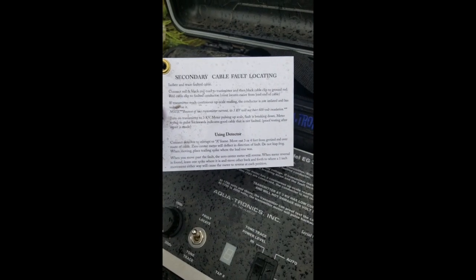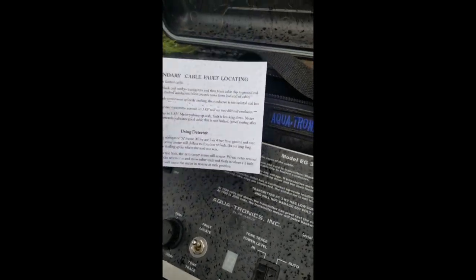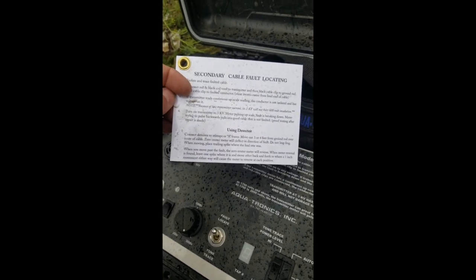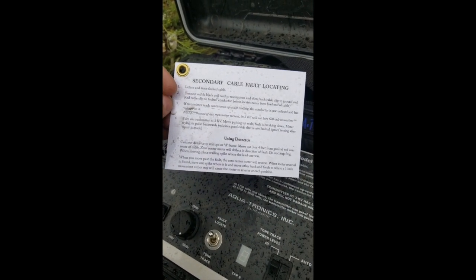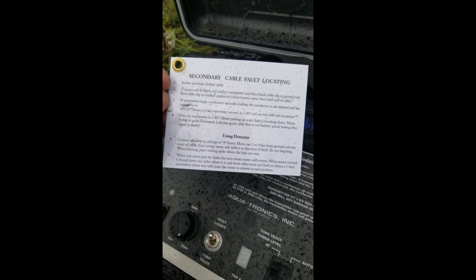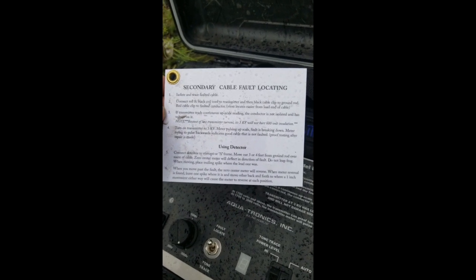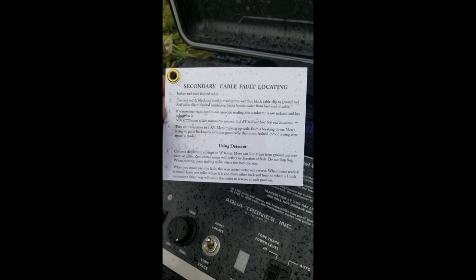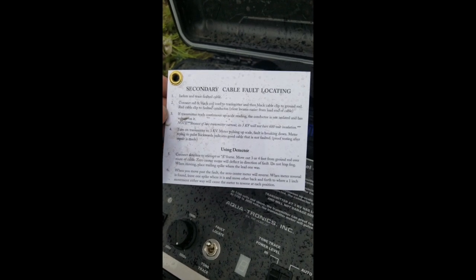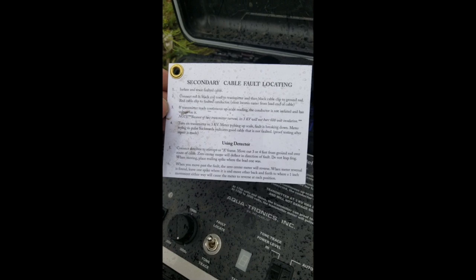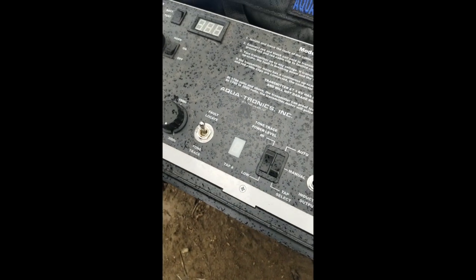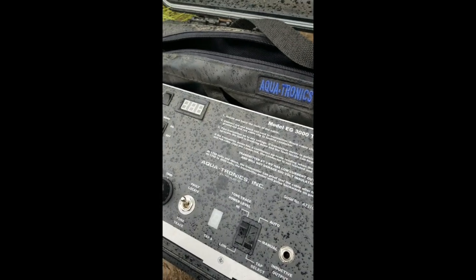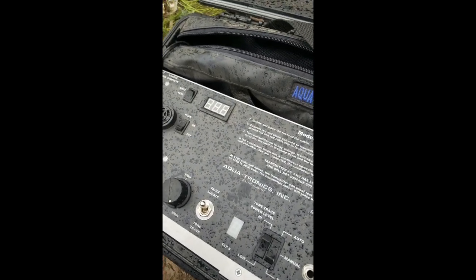This kind of gives you 9 steps basically to follow when going out there, because we all know nobody reads the instruction manuals. This kind of just gives you the basic things that you need to do on a majority of the faults you'll go on. As it says, the first step in any cable fault, don't forget to do it, is trace the cable. That's why we build in those cable tracing functions into this device. So trace the cable. You will save yourself time in the long run.